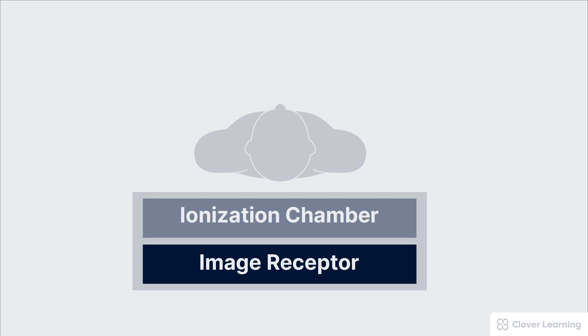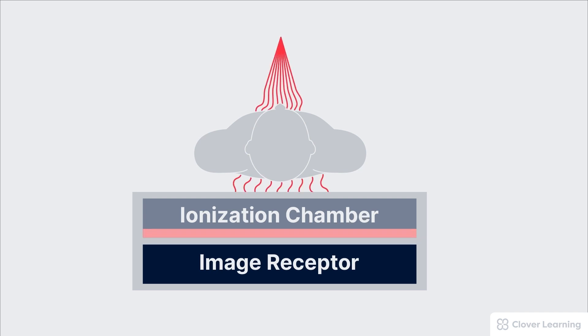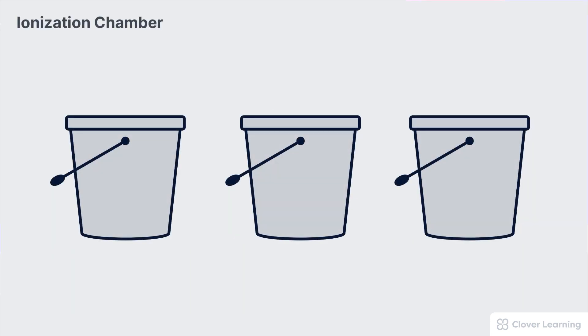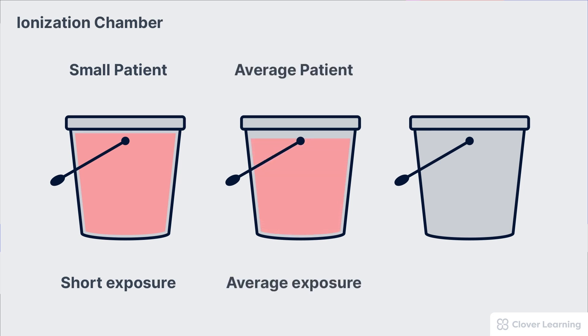Once an exposure is initiated, it continues until the ionization chambers have detected the correct level of exposure to create a good image, and then the exposure is terminated. For every patient, the bucket is the same size, because the receptor exposure needed for a good image is the same. However, smaller patients absorb less radiation, so the buckets fill up fast and the exposure shuts off sooner. Average size patients absorb more radiation, so the bucket takes a little longer to fill. Large patients absorb even more radiation, so the bucket takes even longer to fill.